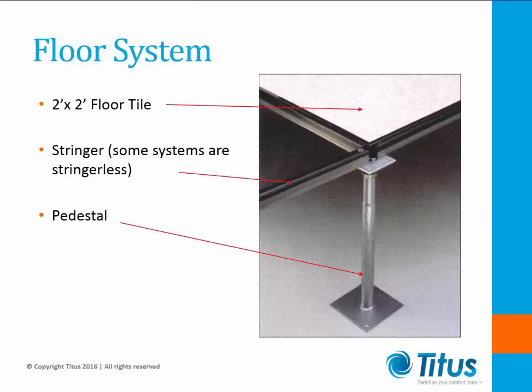The basic components of the raised floor system can be seen in this picture. UFAD systems in North America typically use two foot by two foot square floor panels. The floor panels are made from composite materials, most commonly steel panels filled with a concrete-like material. The panels are supported on their corners by steel pedestals, which are adjustable and typically create floor plenums 6 to 18 inches tall. Some systems use stringers and others mount the panels directly to the pedestals. The floor panels are available without openings or with a variety of pre-punched holes to accommodate floor-mounted air outlets and wiring grommets.